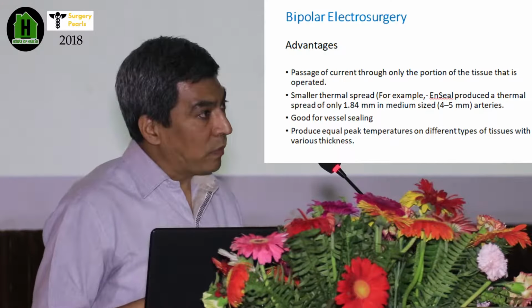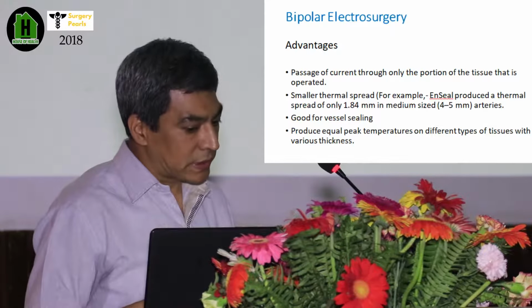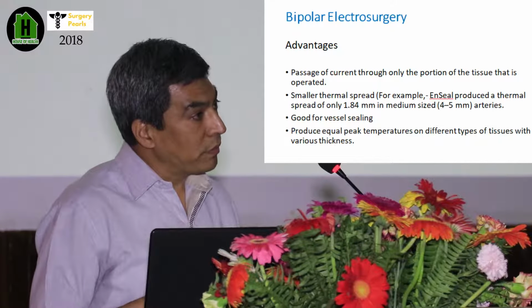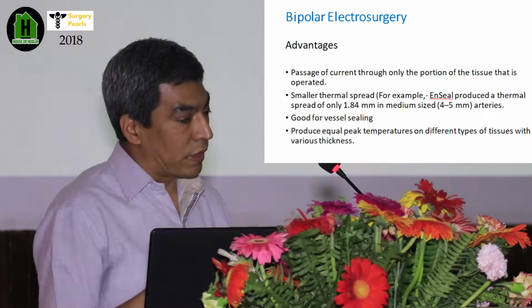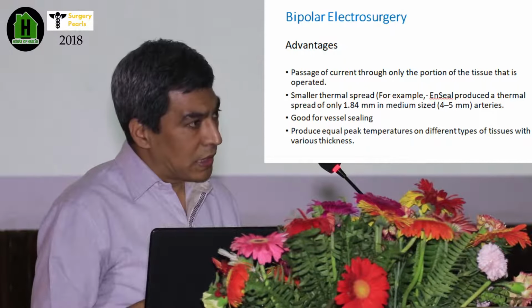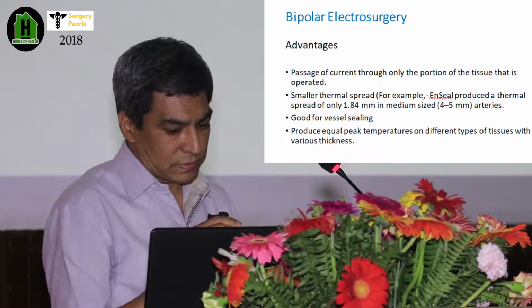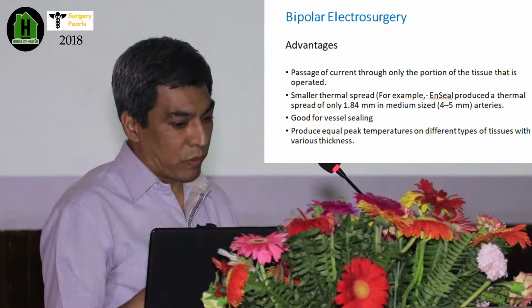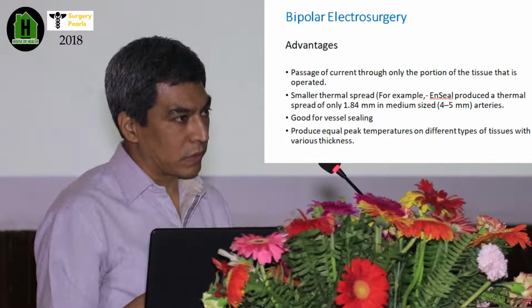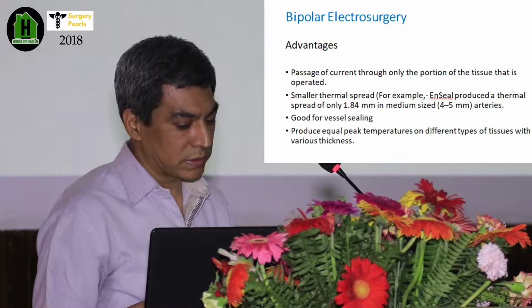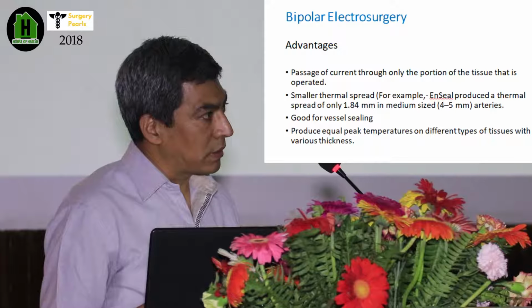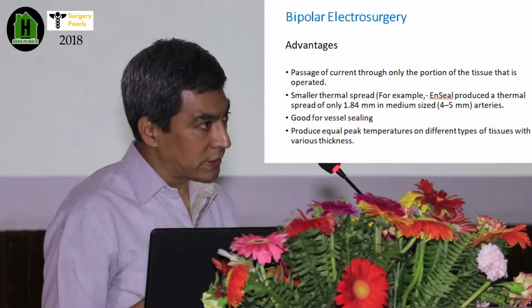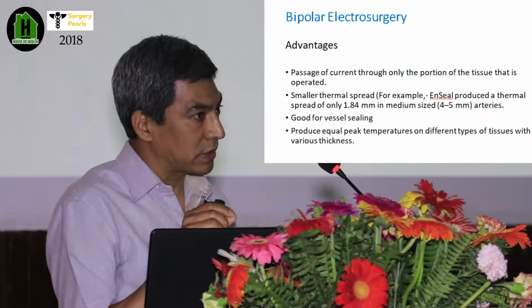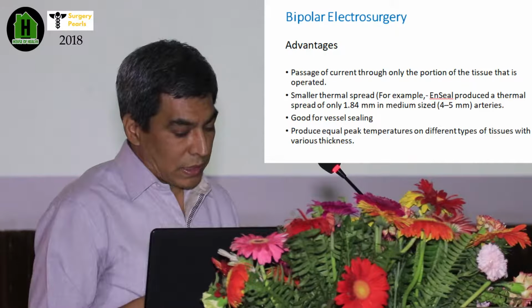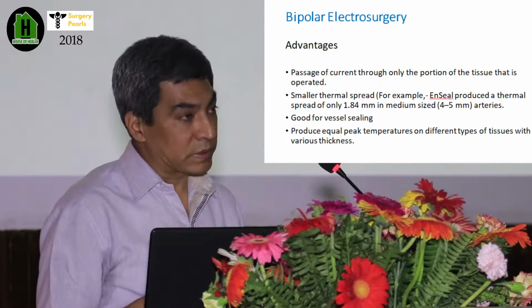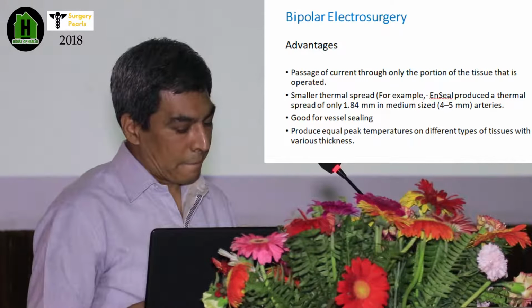Similarly, bipolar electrosurgery has some advantages. The current passes from active to passive electrodes over a very short distance. It will give a very small thermal effect. EnSeal is one of the bipolar electrosurgery units, though this is not only electrosurgery, it has some other combination technology also. It is good for vessel sealing of small vessels. As I said, you have to take the vessel from both sides. And it will give an equal peak temperature on different types of tissue, regardless of the tissue and its thickness.